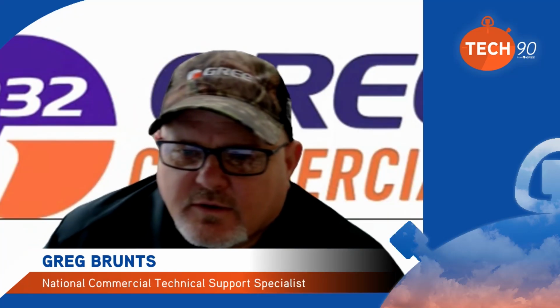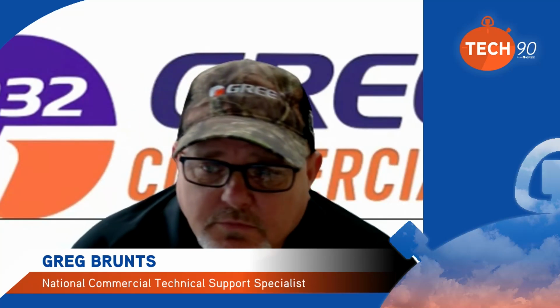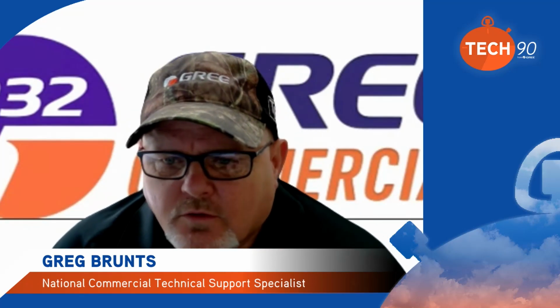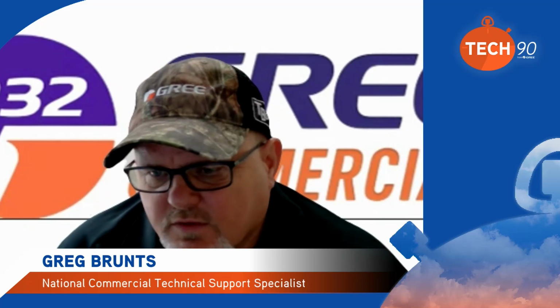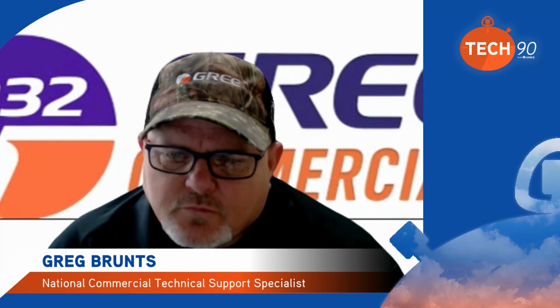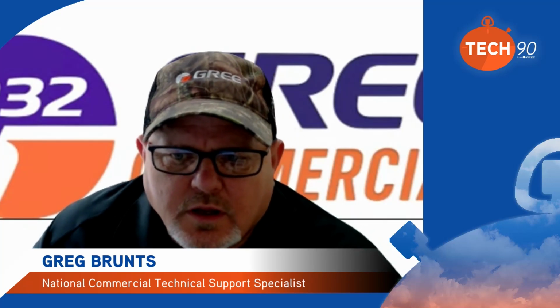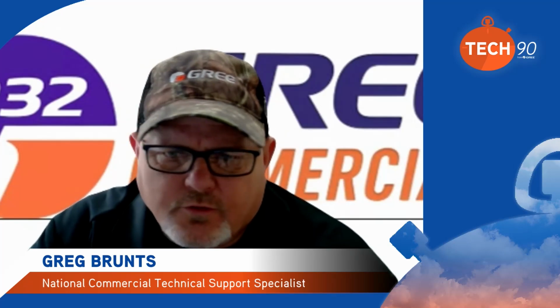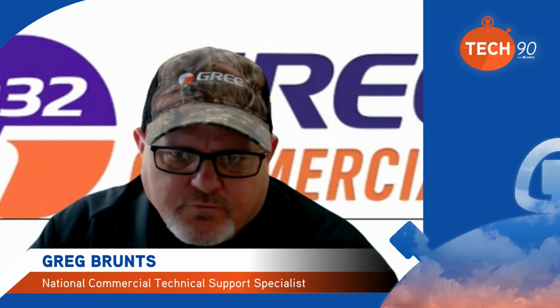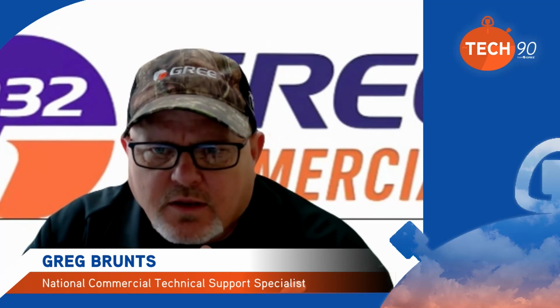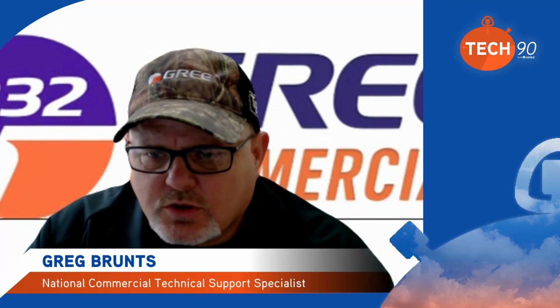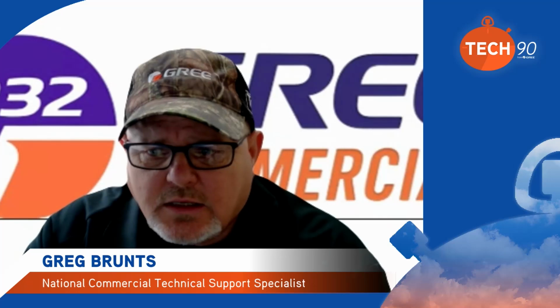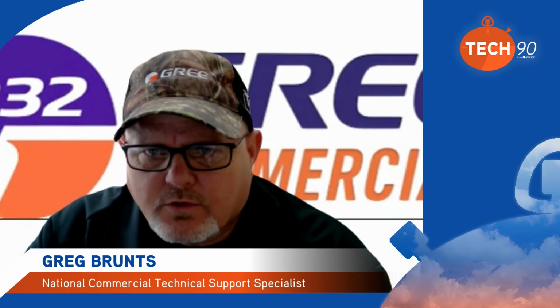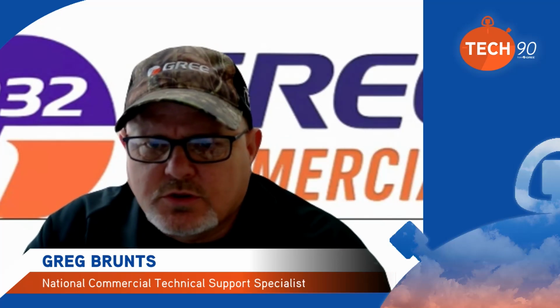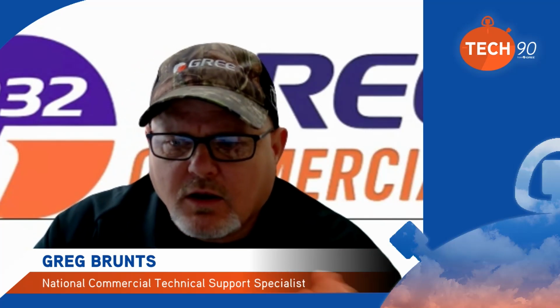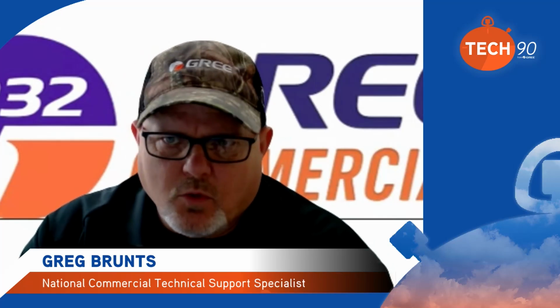All right, today we're going to be talking about MultiPRO startup, troubleshooting, and piping overview. So we're going to have Jesus walking through our quick start guide, which is new for the R32 MultiPRO. Then we'll follow that with a clip from some recent training that I've done with 410A product. But just so you know, the service tool I'm using in that whole training is the same service tool you'll be using for R32, because the pressure temperature differentials and such are based off the board program, not off the tool. So it's just reading what the board is telling it.